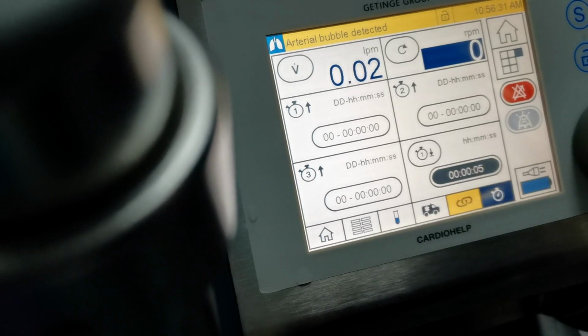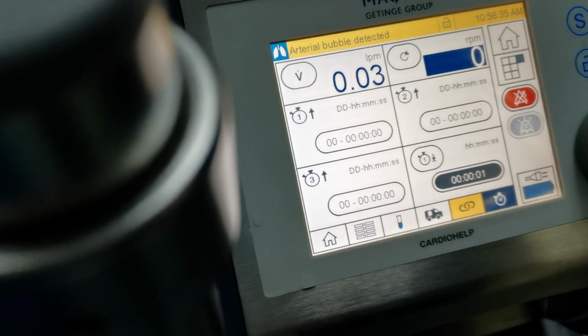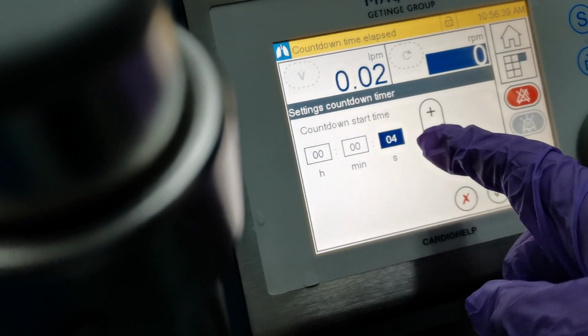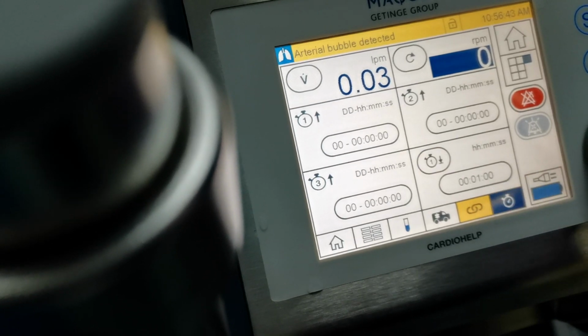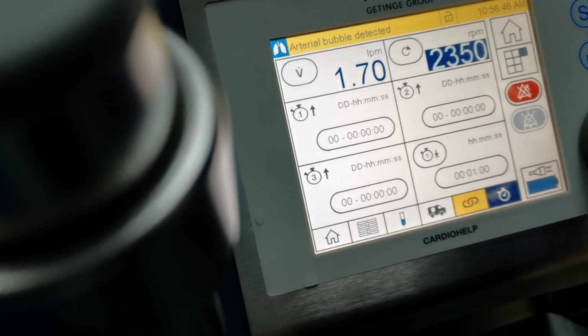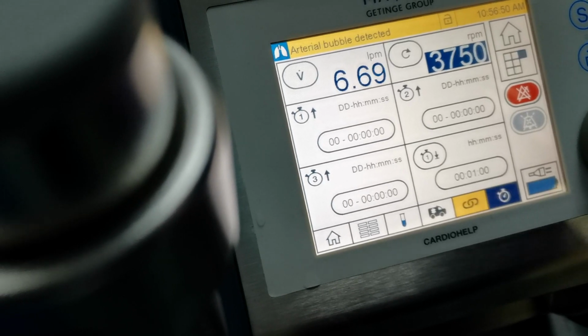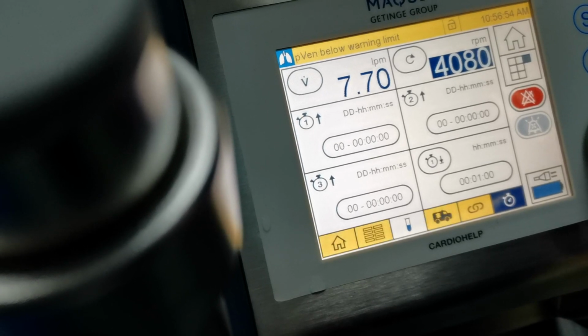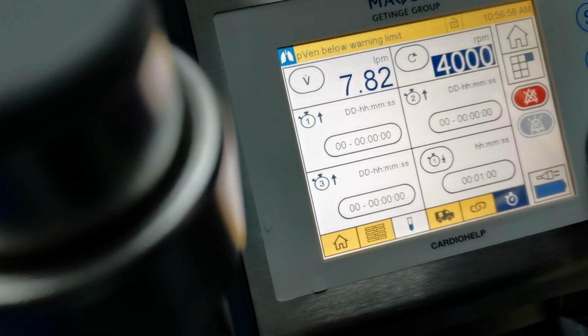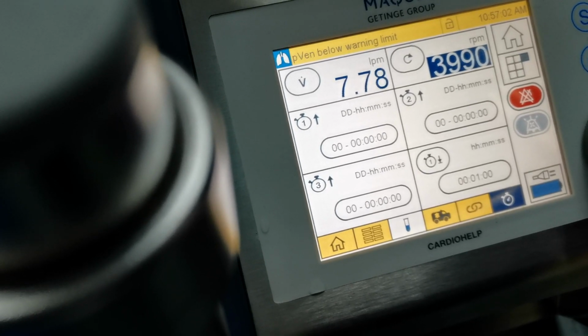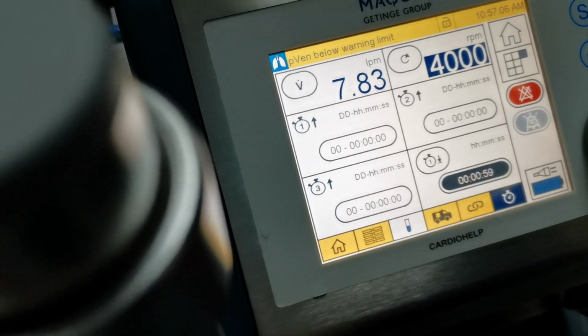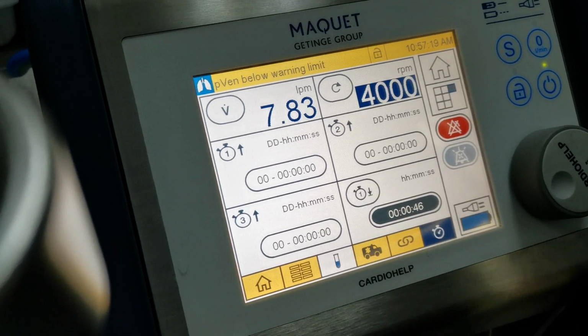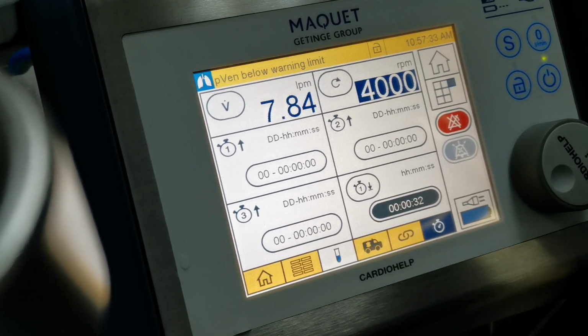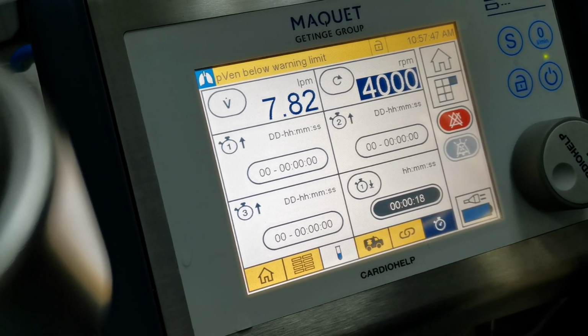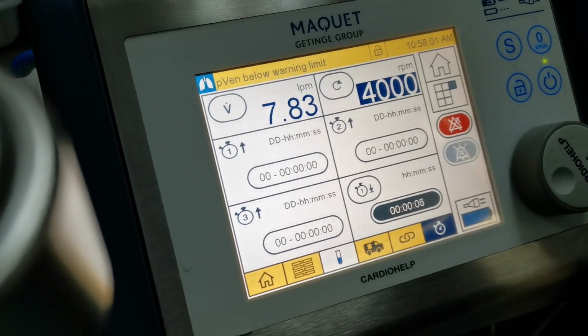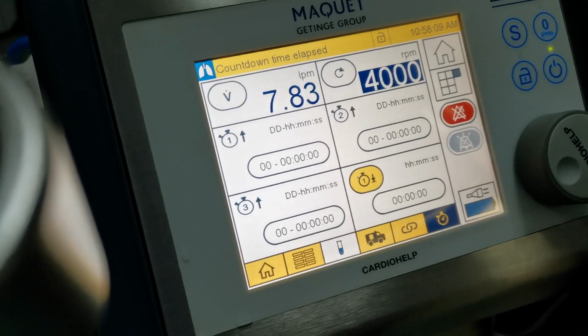After running the pump at 3000 RPM, allow the pump to rest for 5 seconds. Run the pump again at 4000 RPM for at least 1 minute. This is to ensure that all air is eliminated from the circuit. Please take note that no air should be visible and the pump should be virtually silent. After active priming, you may now turn off the pump.